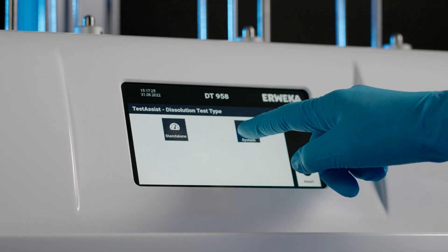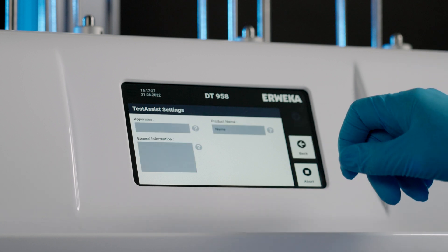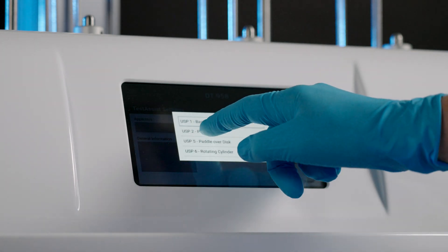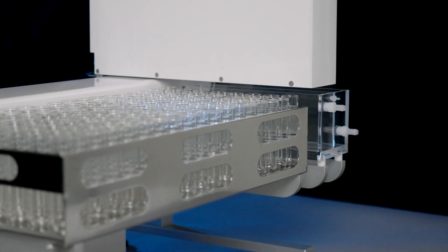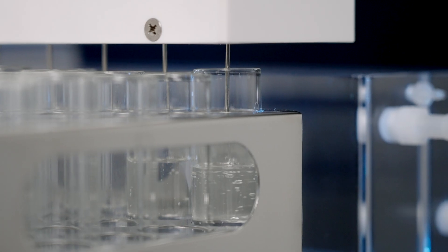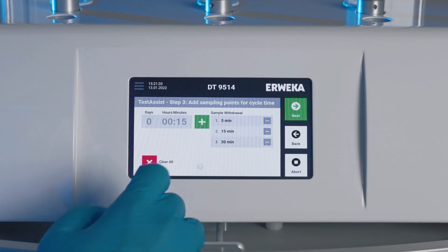The standalone testing mode and the new system testing mode, which enables TestAssist to control the connected automatic sampling station, pump, and sample collector for fully automated, highly precise sample taking and sample storing at user-defined time points.